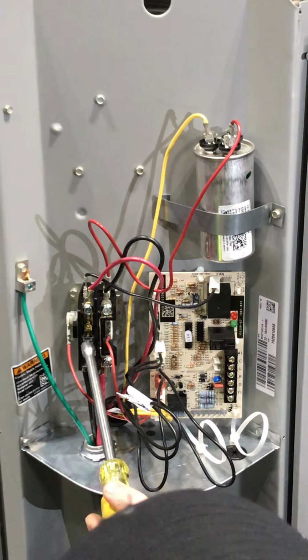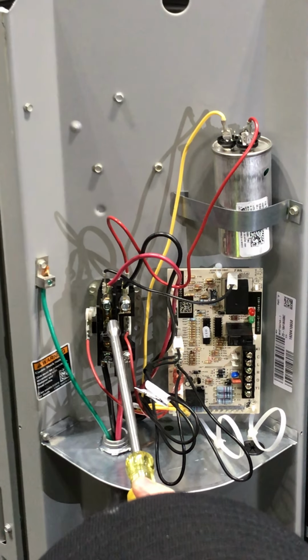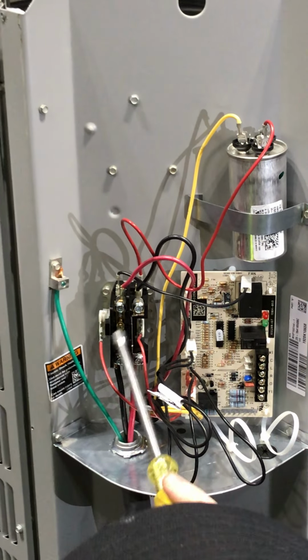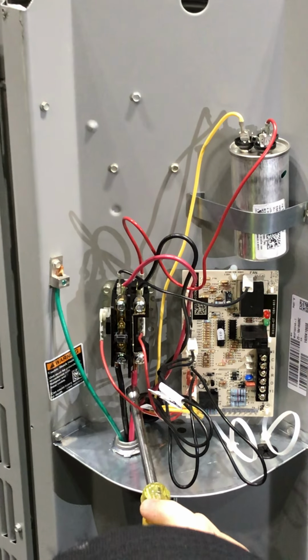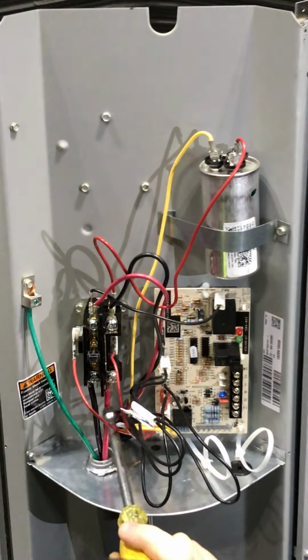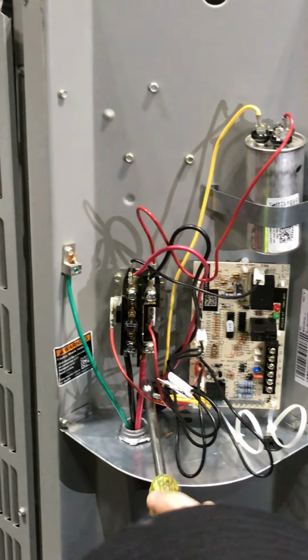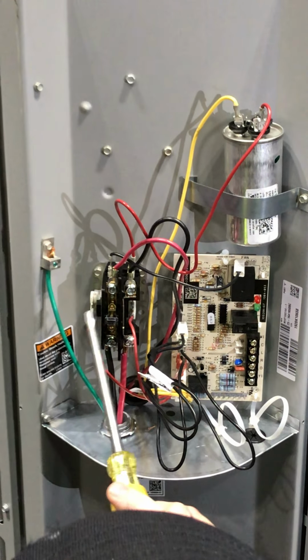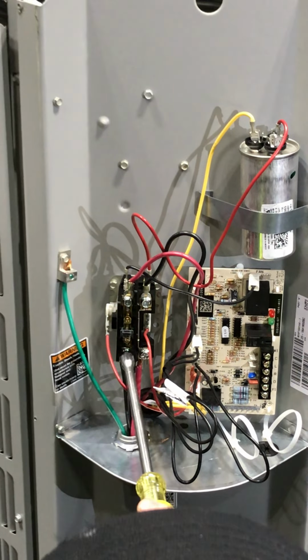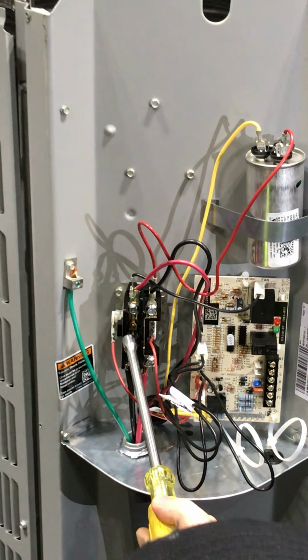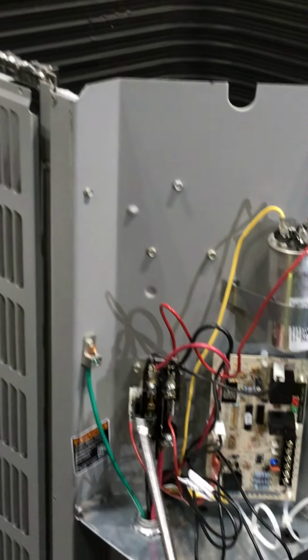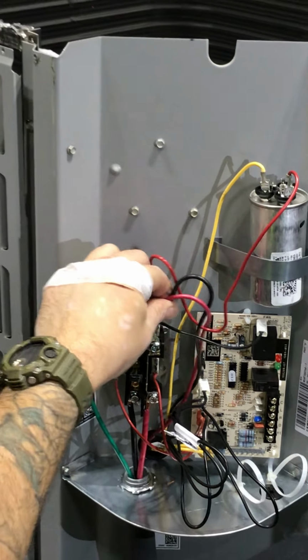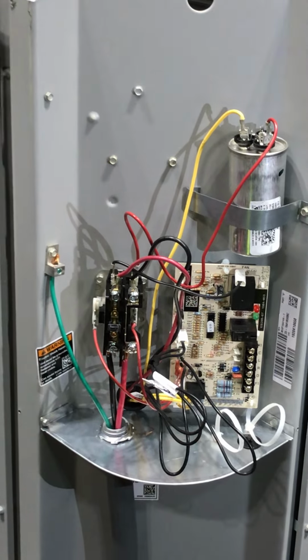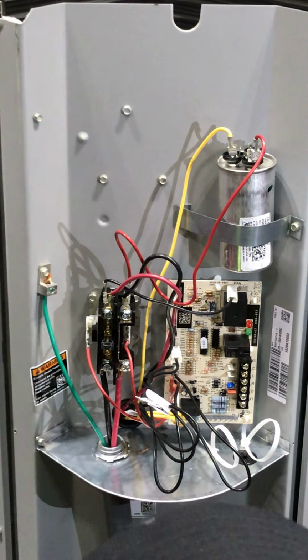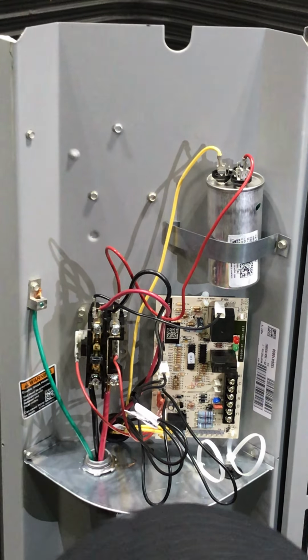Richard, do you understand the function of this guy? Contactor. What's his job? Everything's connected together. So I'm connected with my main power, which is how many volts, Richard? 240. And I'm also connected with my low voltage, which is how many volts? 24. So once this guy's engaged, what's going to happen? It's going to send power from down here up here. So now my compressor, which are these two, has power, and my fan now has power. That's his job, to connect everybody with power. He hooks everybody up with power. We like our contactor. We want to keep our contactor working, right?